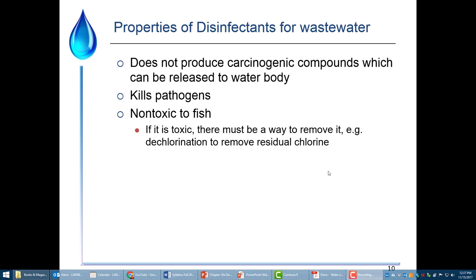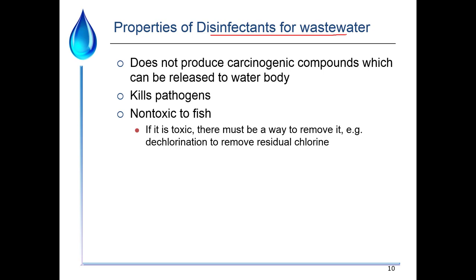In a wastewater treatment context, disinfectants still need to kill pathogens and we still don't want to produce carcinogenic compounds for release into the water body. But here, the disinfectant needs to be non-toxic to fish, or if it is toxic we have to be able to remove it. Chlorine can be dechlorinated by adding different chemicals. In many cases, wastewater treatment has moved toward ultraviolet disinfection because UV is just light — when you turn the light off, there is no residual, which is an advantage.